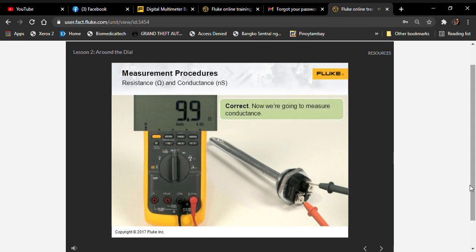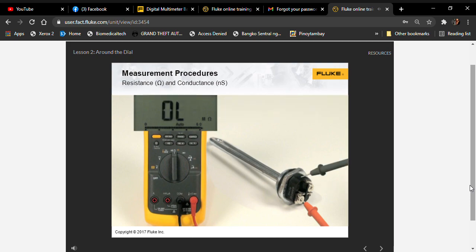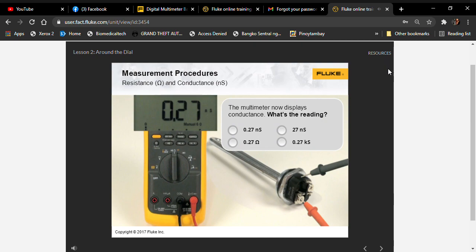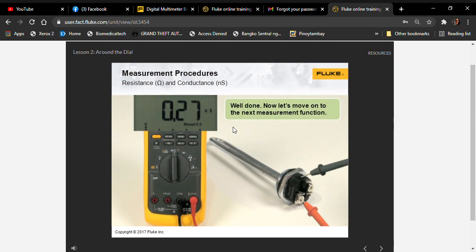Correct. Now we're going to measure conductance, but we need a much higher resistance to do that. About 20 megaohms should do it. We can move one of the test leads to the outer casing of the heating element, which should be insulated from the electrical connections. The multimeter now displays conductance. What's the reading? Well done. Now let's move on to the next measurement function.